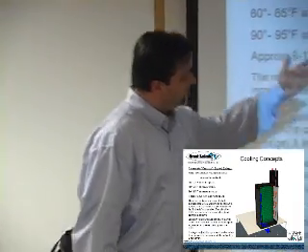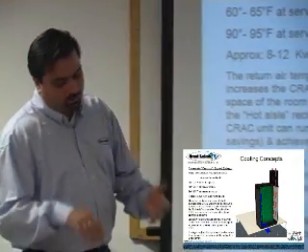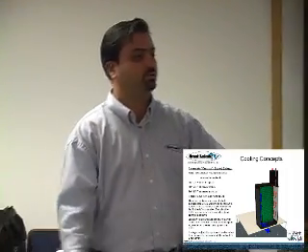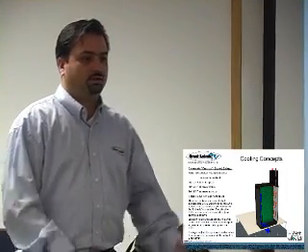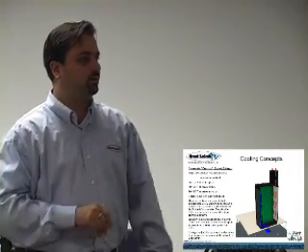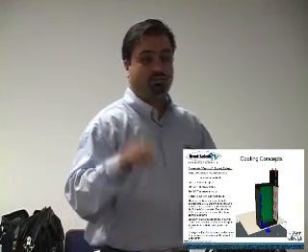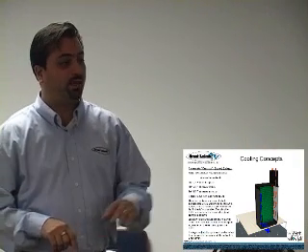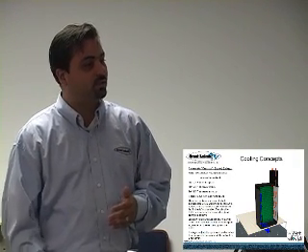Whenever you have a ducted system on the raised floor, when you start cutting holes in the raised floor, you want to maintain the same pressure throughout your data center. If you cut the same hole everywhere, you're going to have pressure drops, where some cabinets are actually going to be pulling down. We've seen that as well. So you have to maintain how close you are and what the velocity is underneath.